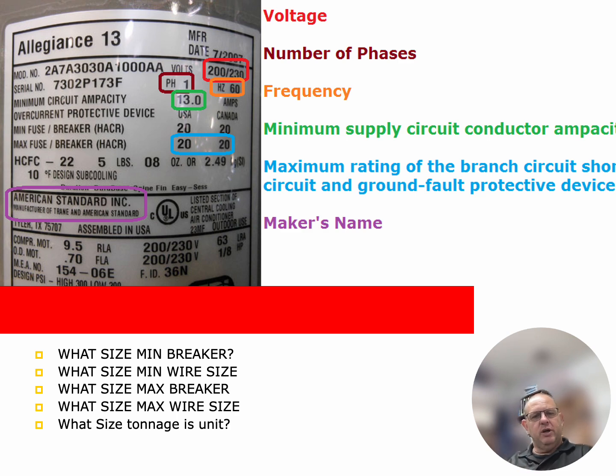Question number 2. Can I install a 10 gauge wire on this system? And the answer is yes, because the 10 gauge wire can take 30 amps, and I have a 20 amp breaker on this circuit that will protect that wire. Remember, the breakers are there to protect the wires so that we do not catch on fire.